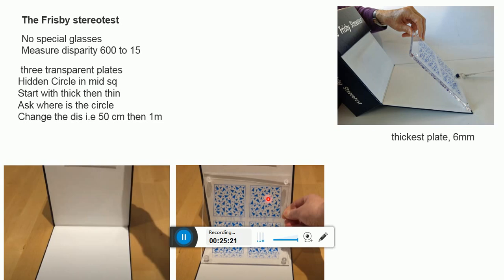At a 40 cm viewing distance, the plates show a disparity of 340, 170 and 55 seconds of arc, and by adjusting the viewing distance, the test can be used to give a disparity range from 600 to 15 seconds of arc.